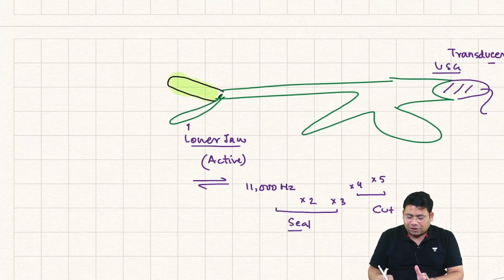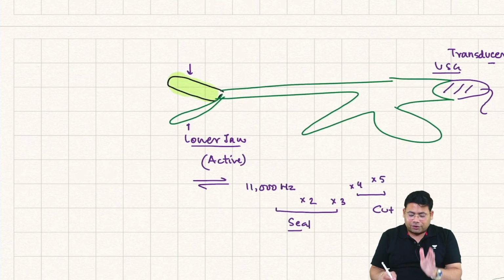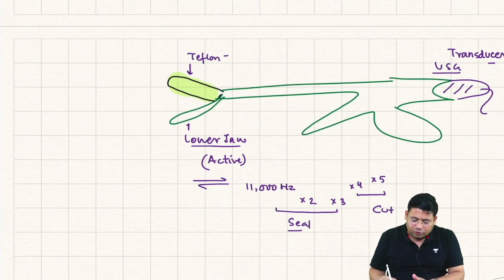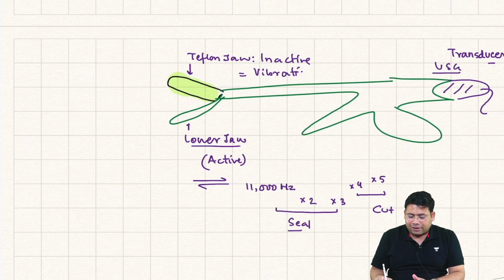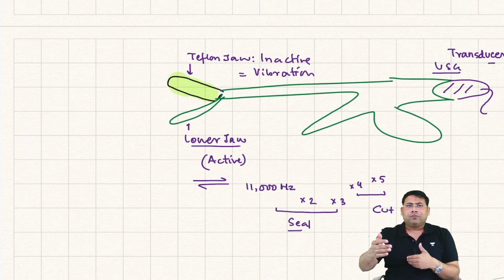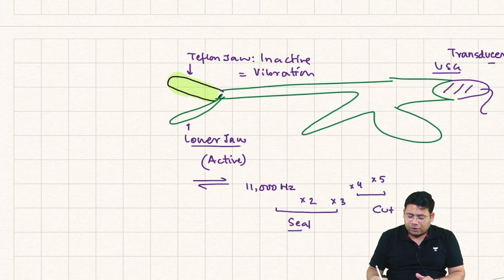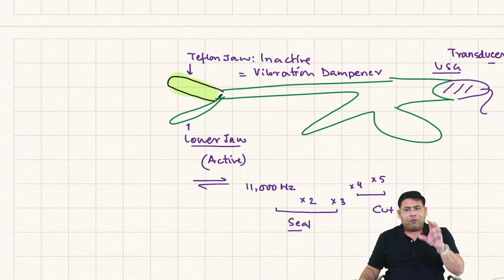Now you must be thinking, what is the significance of this jaw? The upper jaw, that is a Teflon jaw, an inactive jaw, and that is actually the vibration dampener. Basically, when you are touching it against a tissue, the vibrations can knock off the nearby tissue, and that is why there is a Teflon jaw. Remember, if this Teflon jaw is damaged, the instrument should not be used. Why? It becomes very dangerous. Try to see again, white jaw, black jaw, and then if you see this instrument, there is a cavity behind.